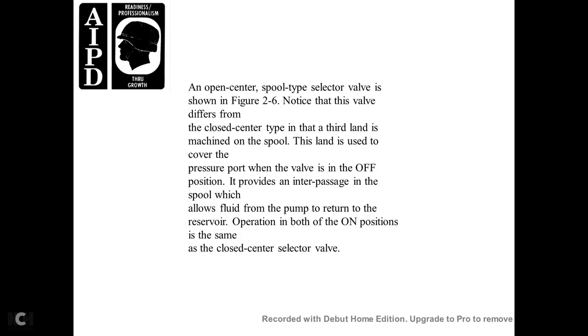An open-center spool-type selector valve is shown in figure 2-6. This valve differs from the closed-center type in that a third land is machined in the spool. The land covers the pressure port when the valve is in the off position but provides an inner passage in the spool, allowing fluid to flow from the pump to return to the reservoir. In both on positions, the valve functions the same as the closed-center selector valve.